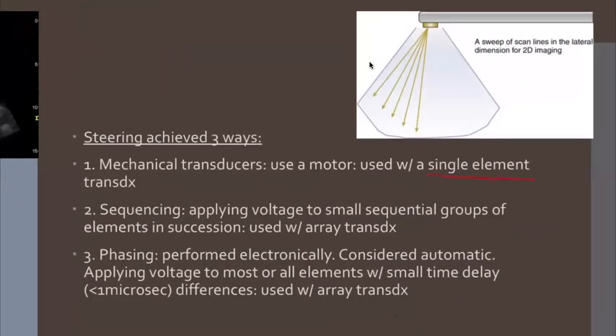I want you guys to link up the words mechanical motor, double M, mechanical motor. Sometimes they're called mechanical transducers, and they're just going to tell you a mechanical transducer - they're not going to tell you a mechanical transducer has a motor. So you're the one that has to remember that a mechanical transducer has a motor. I often say mechanical motor together, and that helps me remember there's that little itty bitty motor and it rotates the crystal, and every time it rotates that one crystal... Remember, I also told you guys to draw that little picture with the one PZT, that one disc-shaped PZT, and that little arrow helps me remember that the motor is turning that PZT.